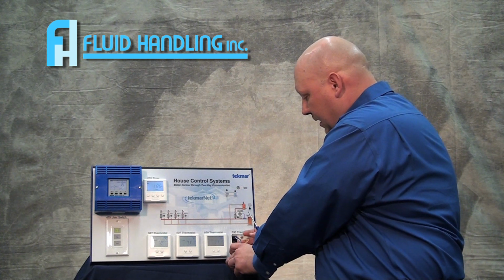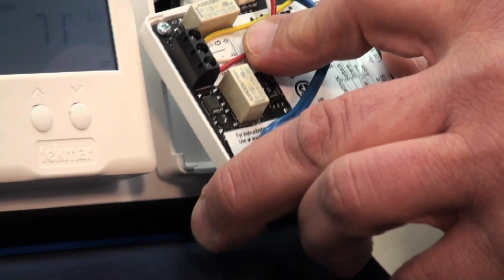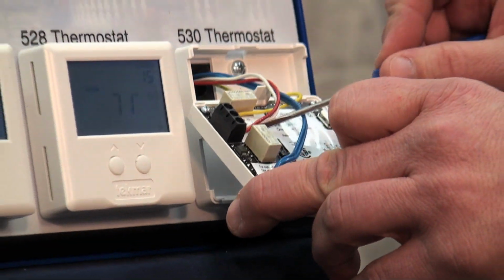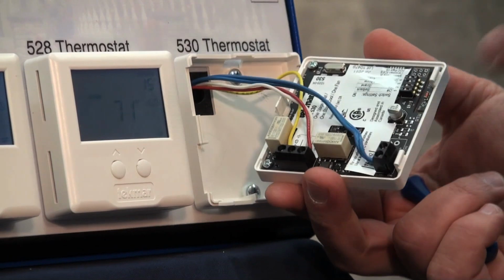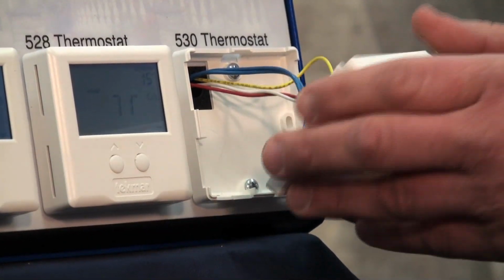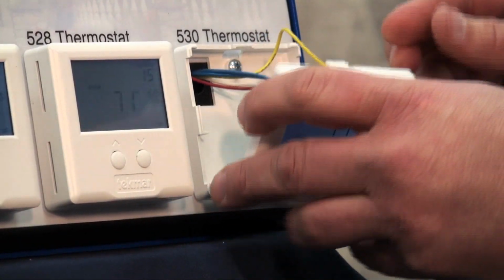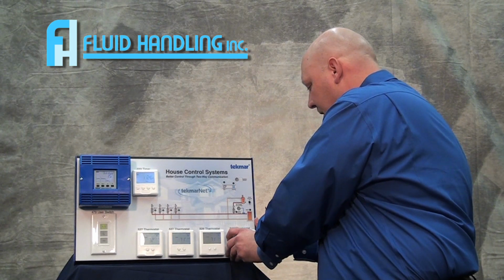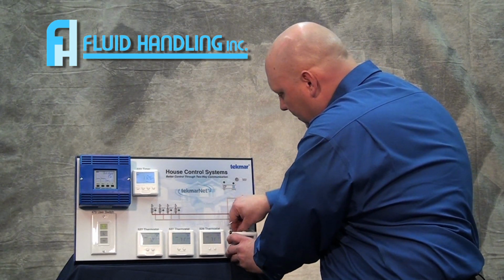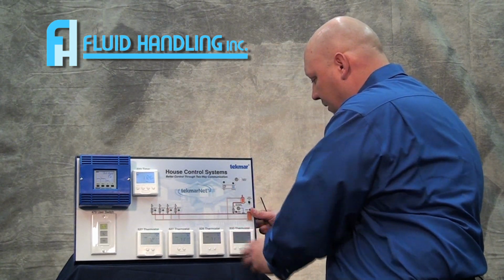This one on the 530, it's kind of cool because we're controlling the cooling here. So here's your R, your Y, and your G that's going to go to your air handling unit for your air conditioning. So that is our 530 stat. And you have the same sequence for putting it back on.